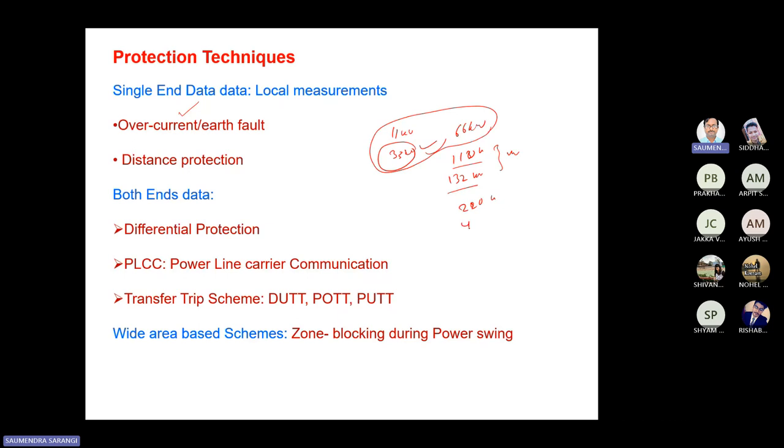And above that, like the 220 kV or 400 kV system, basically they are the transmission line system. If I'm talking about the overcurrent relay, up to 66 kV we use this OC principle, the overcurrent relay. It means only one input will be there to the relay, that is from the CT, and the CT will be connected to the circuit breaker, and it will give the signal. We may talk about what type of circuit breaker we use in the distribution system. Basically, low-cost circuit breakers, either oil circuit breaker or vacuum circuit breaker, are used for the distribution system up to 66 kV.